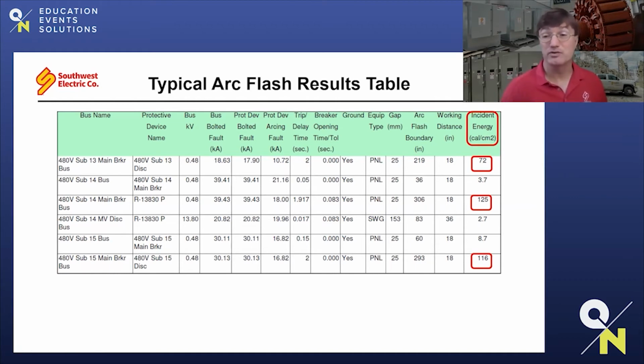So these are very high levels. You can tell if 1.2 causes a second degree burn, imagine what 125 calories per square centimeter would cause. These are extremely high levels, very dangerous to personnel. What I want you to notice now is what is the relationship between the high incident energy levels and the trip delay or clearing time for those potential faults. You can tell those high energy levels result from the highest trip or clearing times that are calculated. You can see that the highest is going to be 2 seconds, and that comes from NFPA 70E. 2 seconds is the given maximum amount of time that an individual would stand in front of an arc flash event.